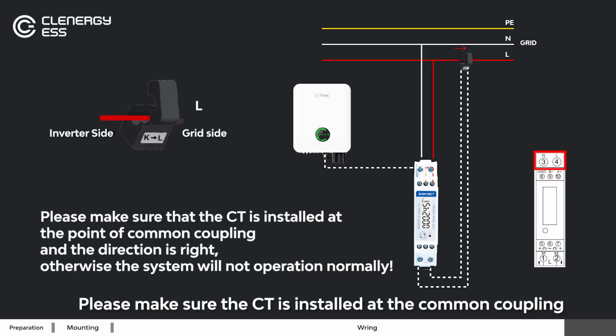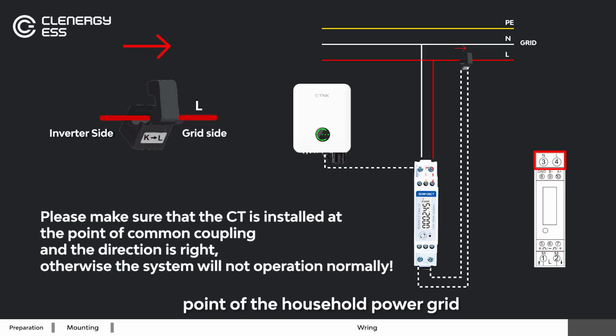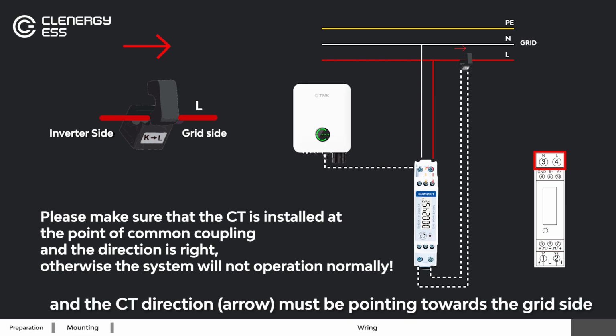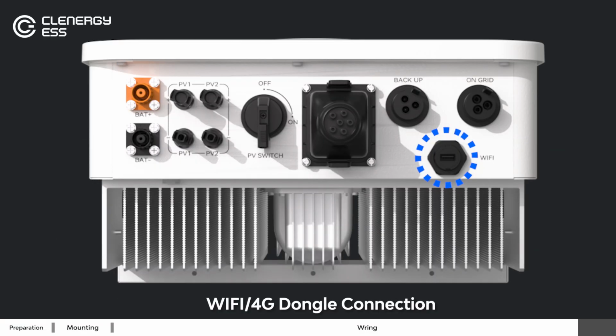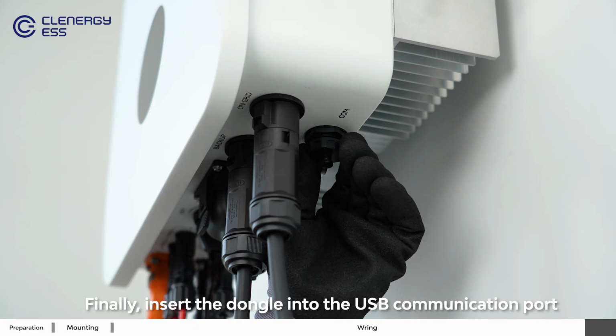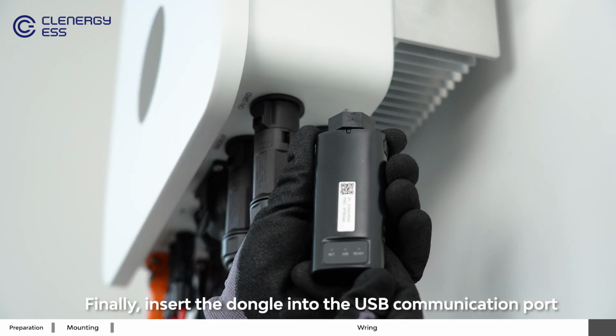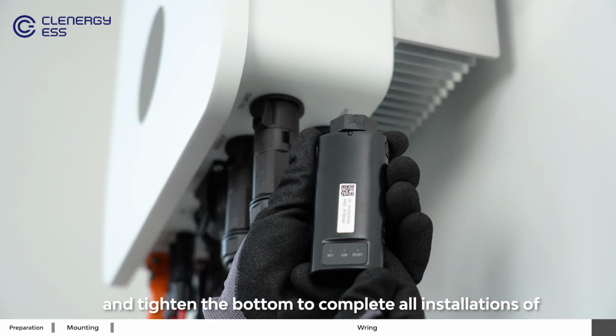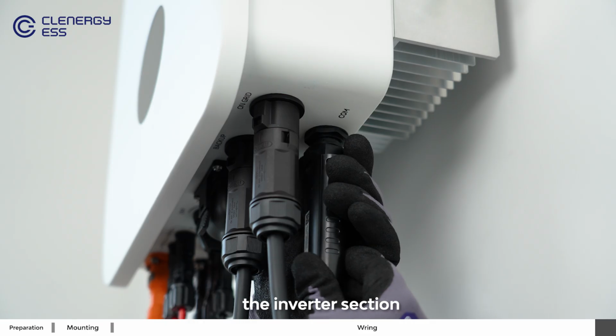Please make sure the CT is installed at the common coupling point of a household power grid, and the CT direction must be pointing towards the grid side. Wi-Fi dongle connection. Finally, insert the dongle into the USB communication port and tighten the bottom to complete all installations of the inverter section.